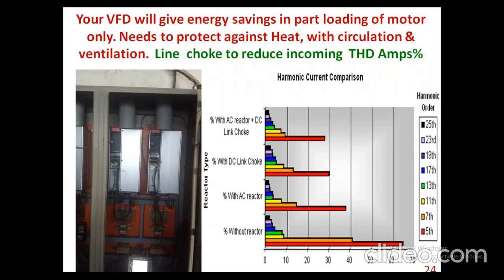Once a VFD is fixed on any of the machines, like the waste collection blower or the axial flow machines, we have to see that the VFD is not put on a machine which is already in an overloading condition. A VFD can deliver its excellent energy saving only when the machine is operated at part loading. When the machine is already running at 100% load, take any compressor: a 75 kilowatt compressor will run at almost 95 kilowatt, because it is always operated at a service factor of 1.2.